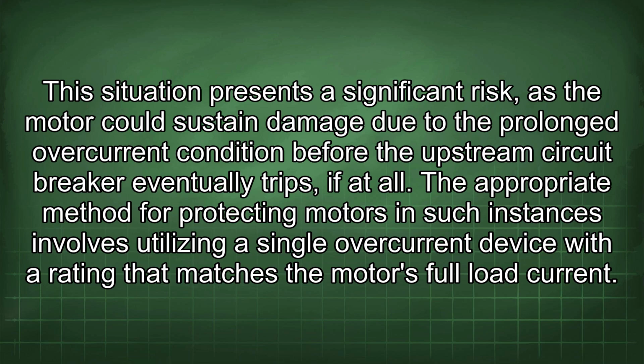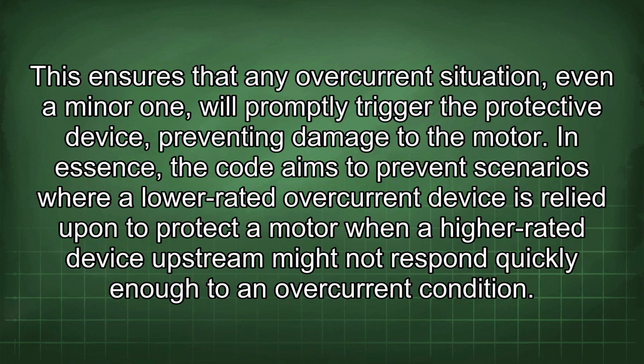The appropriate method for protecting motors in such instances involves utilizing a single overcurrent device with a rating that matches the motor's full load current. This ensures that any overcurrent situation, even a minor one, will promptly trigger the protective device, preventing damage to the motor. In essence, the code aims to prevent scenarios where a low-rated overcurrent device is relied upon to protect a motor when a high-rated device upstream might not respond quickly enough to an overcurrent condition.